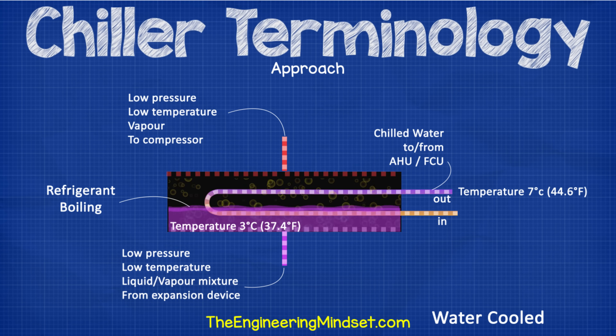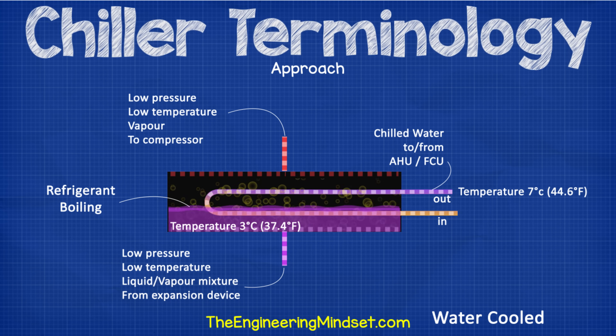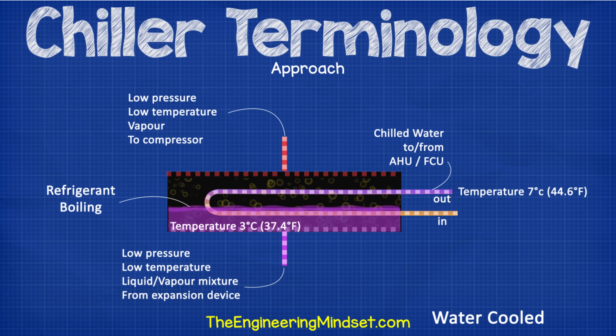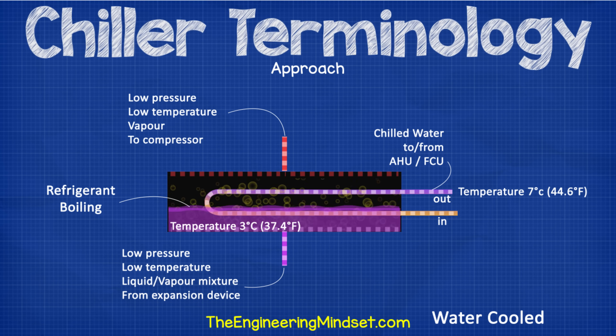Approach temperature. This refers to the temperature difference between the chilled water supply temperature as it exits the chiller compared to the temperature of the refrigerant within the evaporator. For example, the chilled water supply temperature might be 7°C (44.6°F) and the refrigerant might be at 3°C (37.4°F). The approach would therefore equal 4°C (7.2°F). A difference of 3 to 5°C (5 to 8°F) is fairly typical.